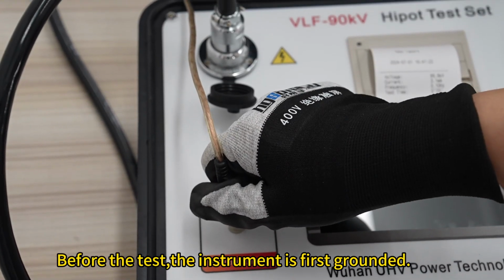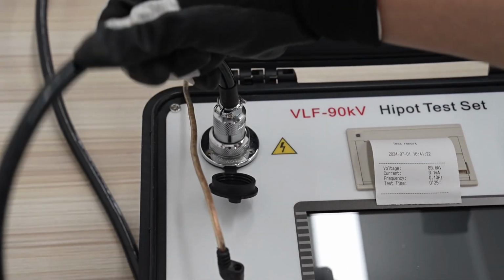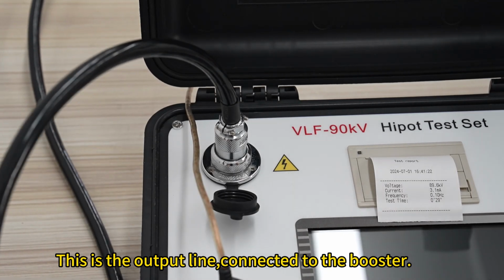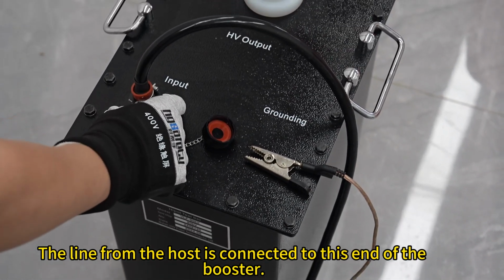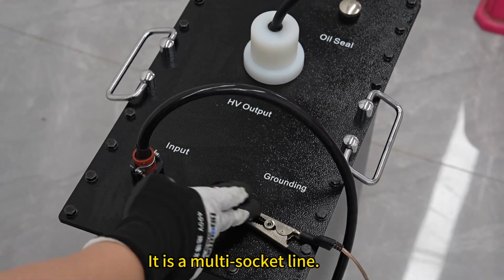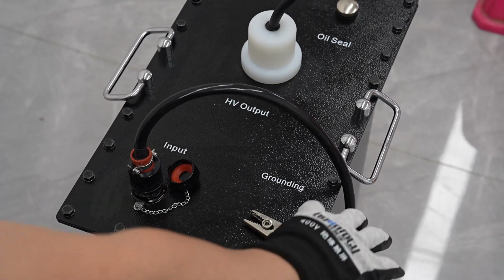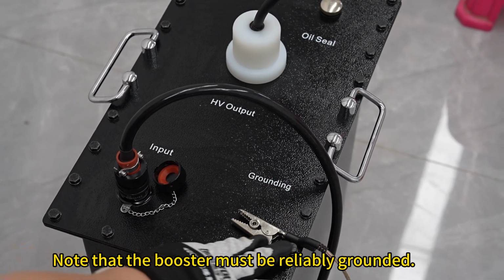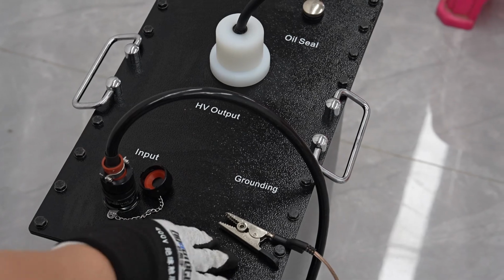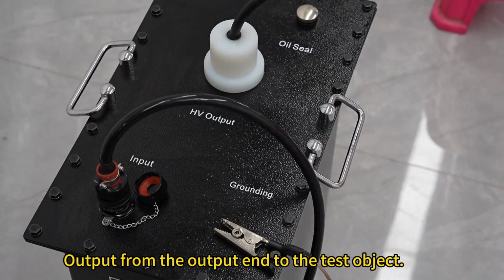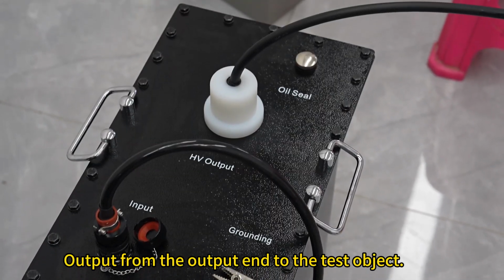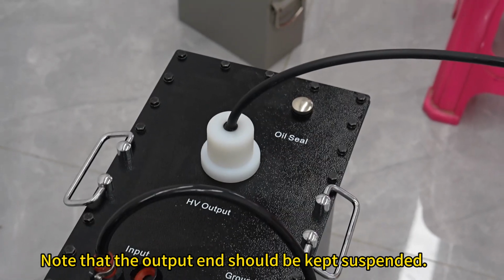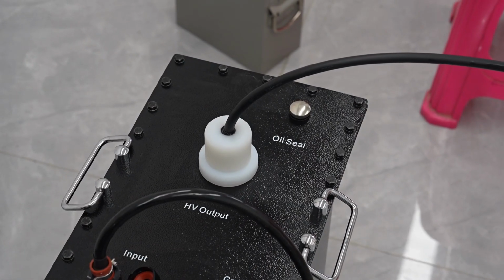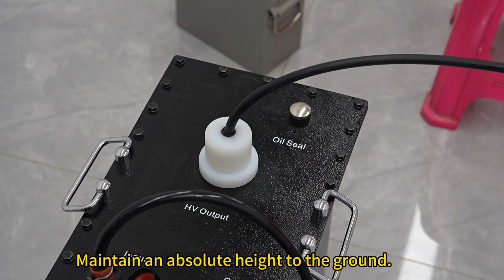Before the test, the instrument is first grounded. This is the output line, connected to the booster. The line from the host is connected to this end of the booster. It is a multi-socket line. Note that the booster must be reliably grounded. Output from the output end to the test object. Note that the output end should be kept suspended. Maintain an absolute height to the ground.